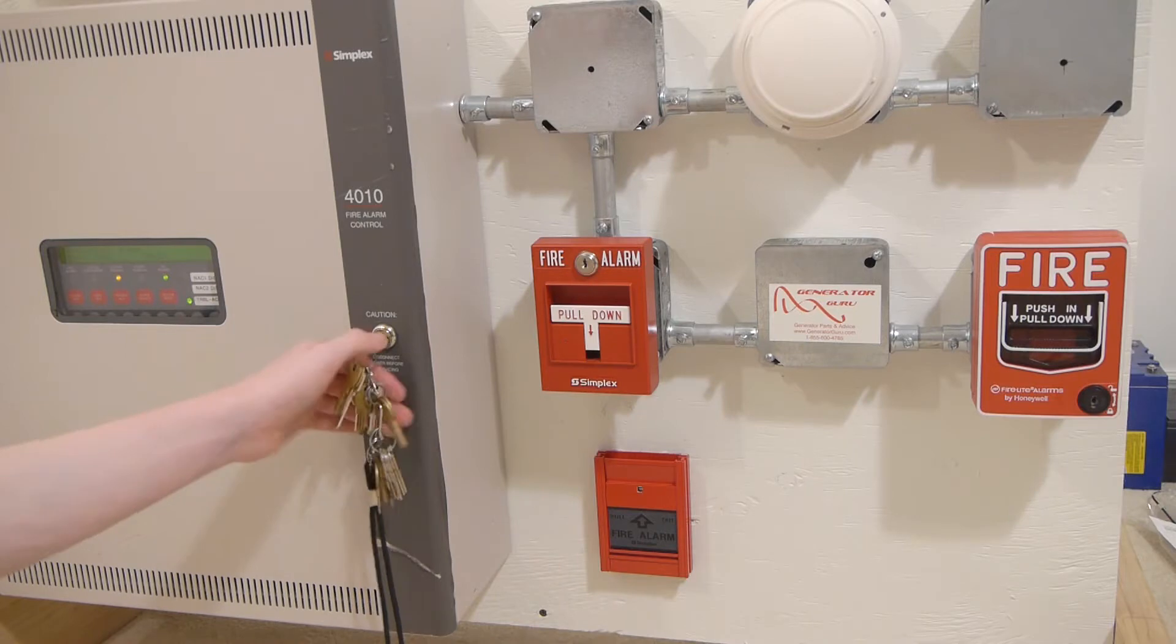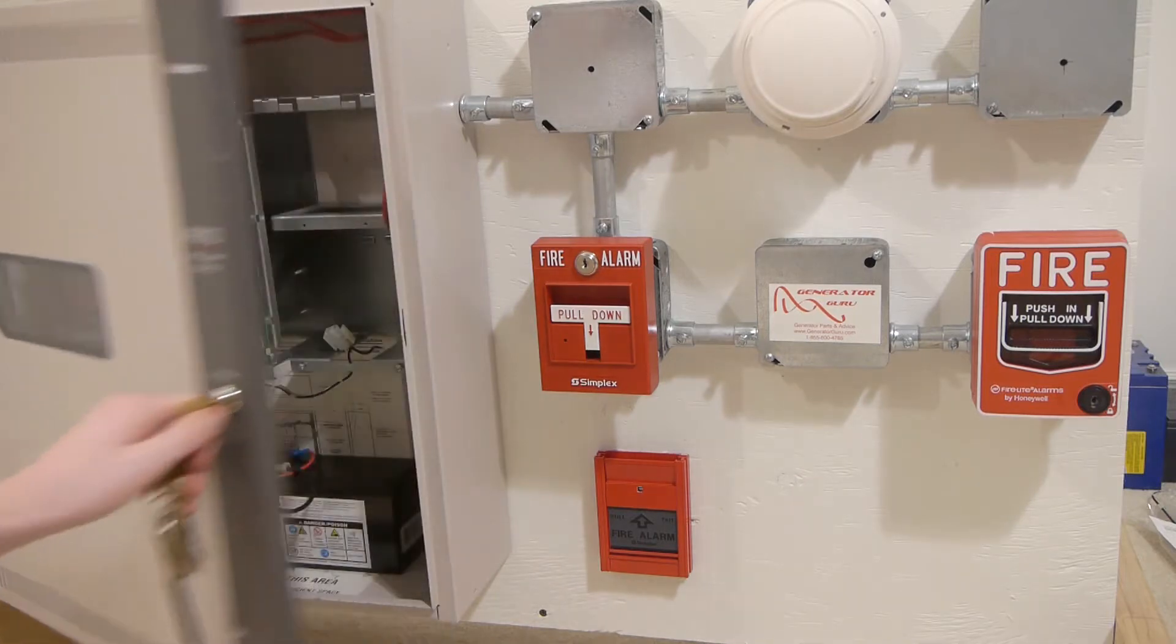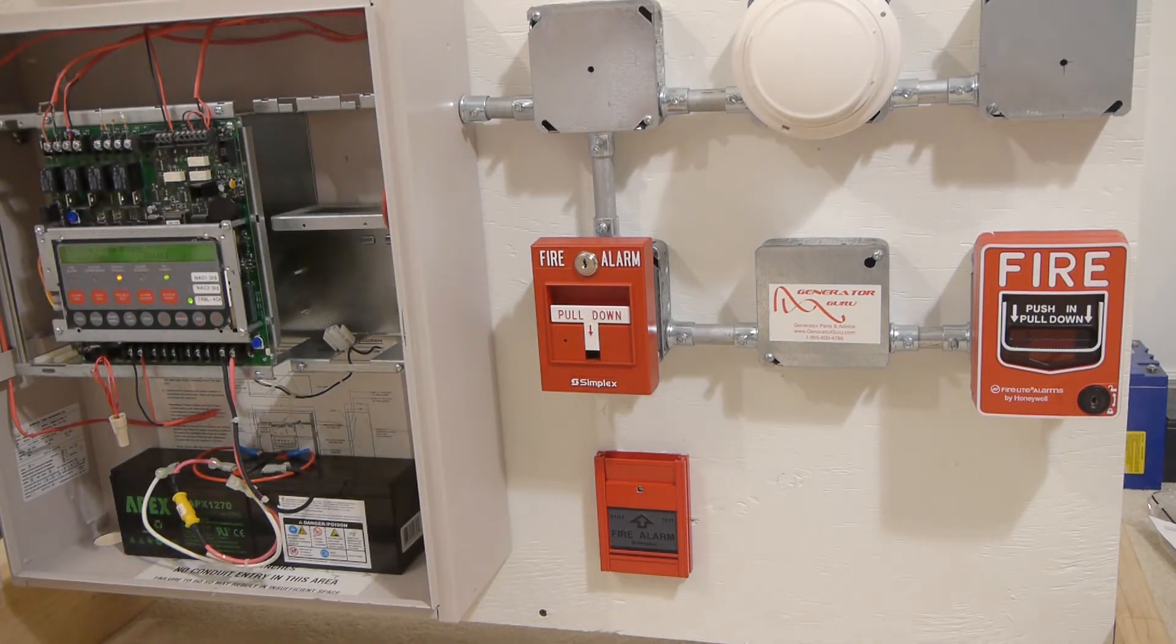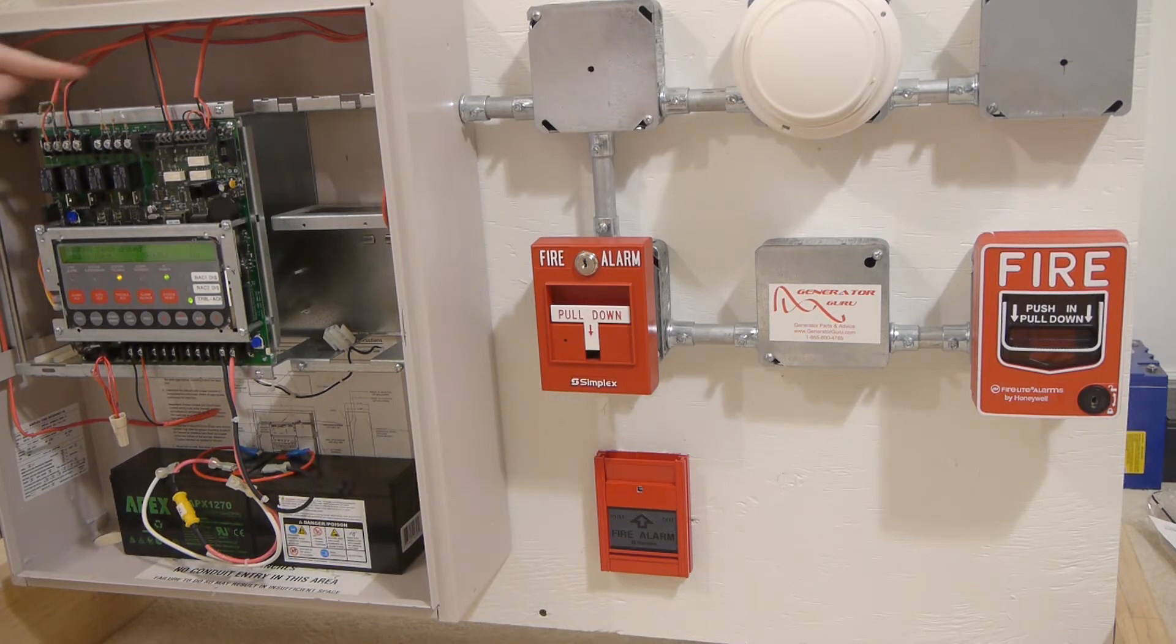Now I know this is on the SLC circuit of the panel, but if you don't know if it's on the SLC, NAC, or any other circuit, you basically just take the positive or negative wire off of each circuit depending on if it's negative or positive earth ground fault until the ground fault goes away.